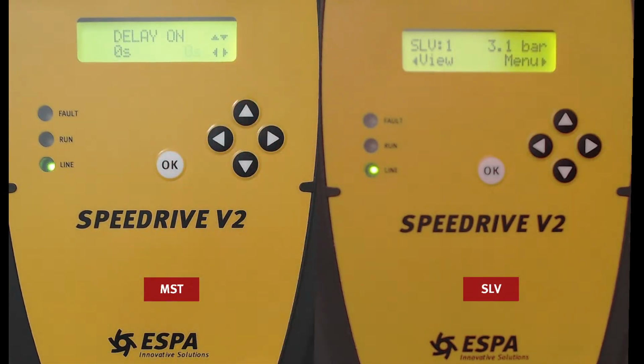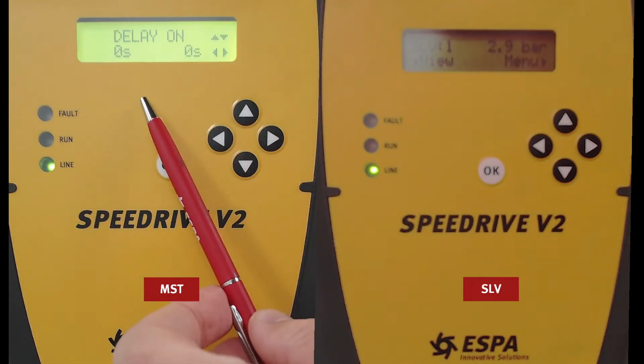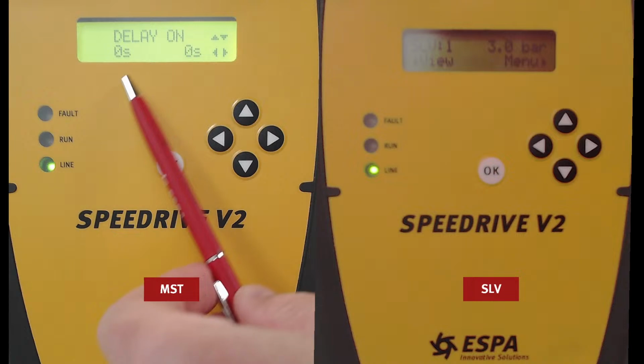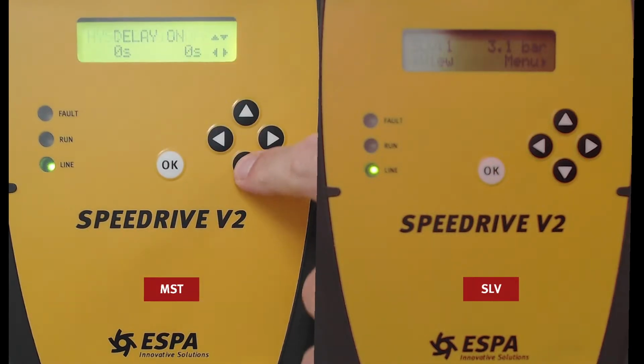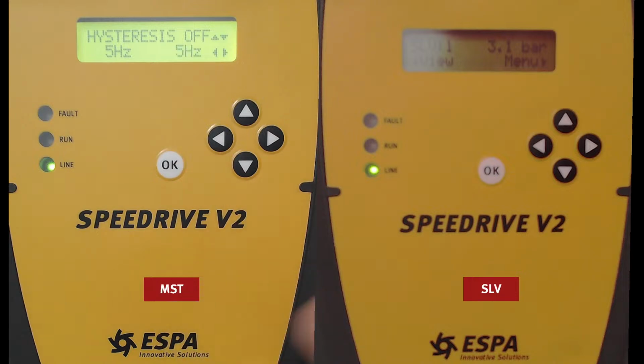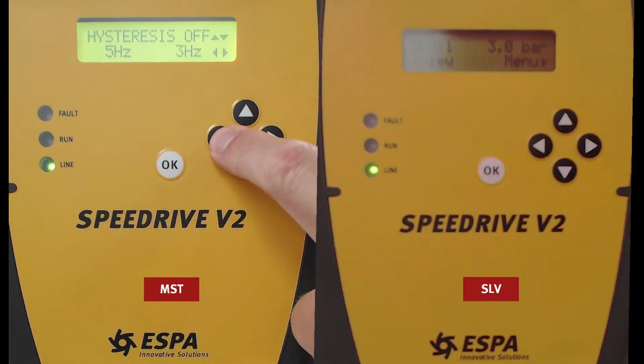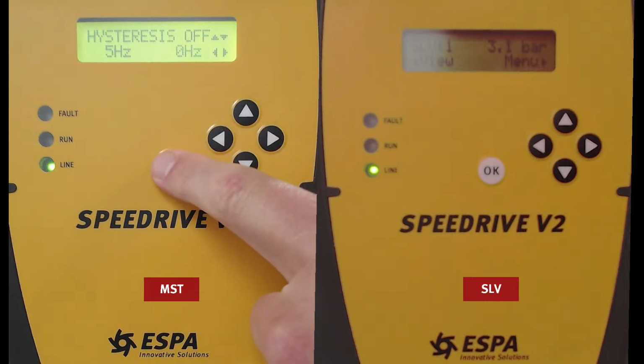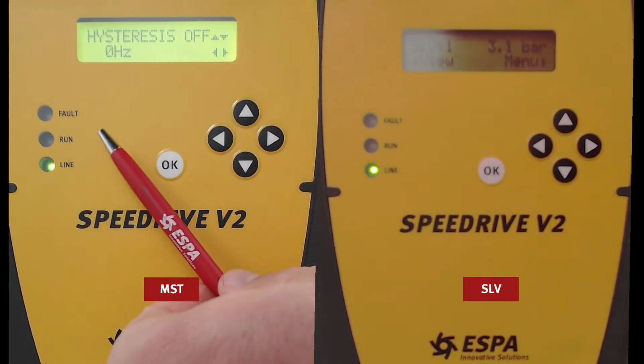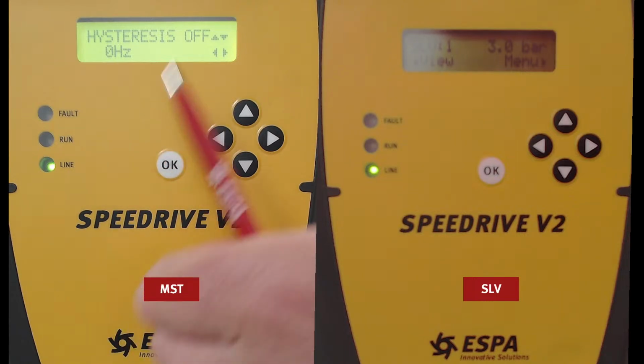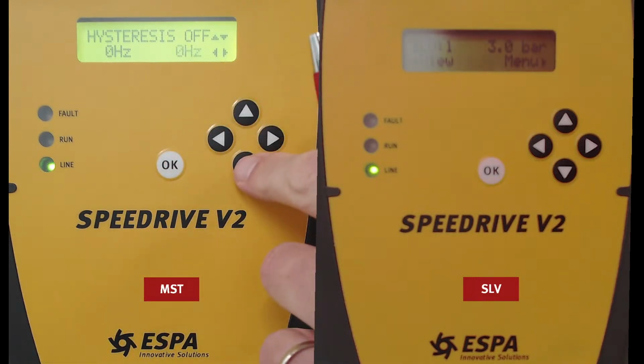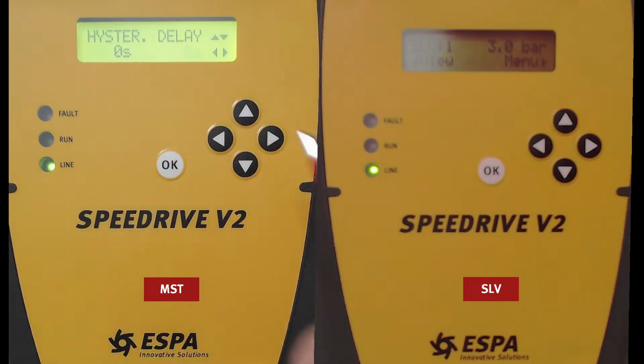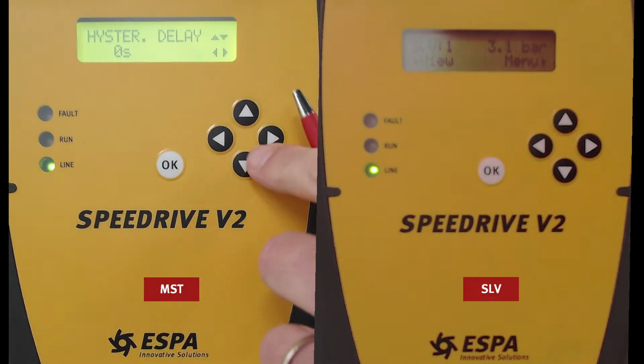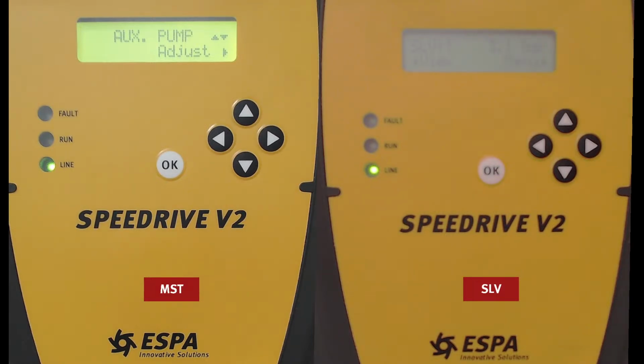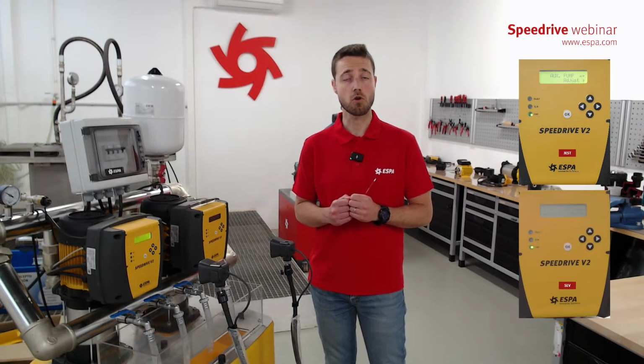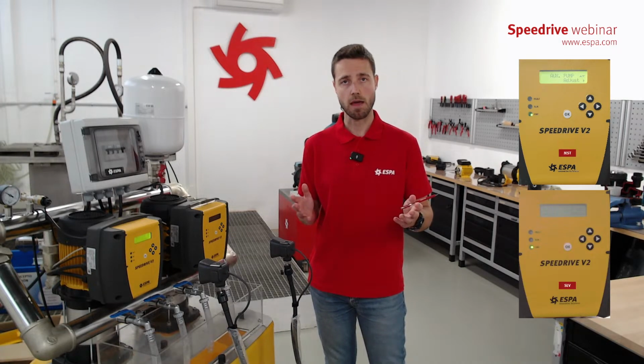Delay. This is just a delay for when we reach the 45 Hertz that we have seen, if we want a delay or not. Hysteresis off. This is a setting that normally is set up by default at 0. It's just the gap between the stop of the master and the slaves. And the same, we can always introduce a delay if desired. So these are the 4 adjustments or settings variables that we can make with our auxiliary pumps.